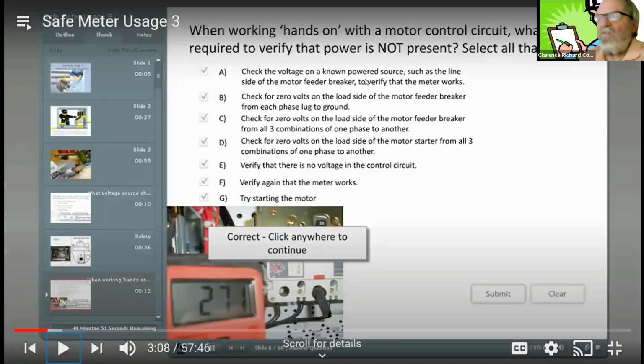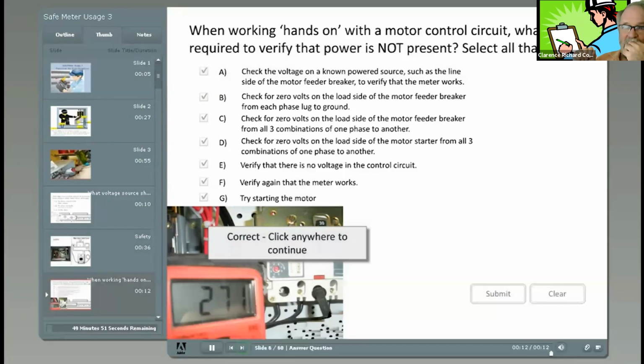Okay, so we went from breaker to the motor starter. I'm not sure the motor starter feeds the motor. That's a little bit overkill, but the circuit breaker is what you wanted to shoot for. E, verify that there is no voltage in the control circuit. F, verify again that the meter works. And G, try starting the motor.